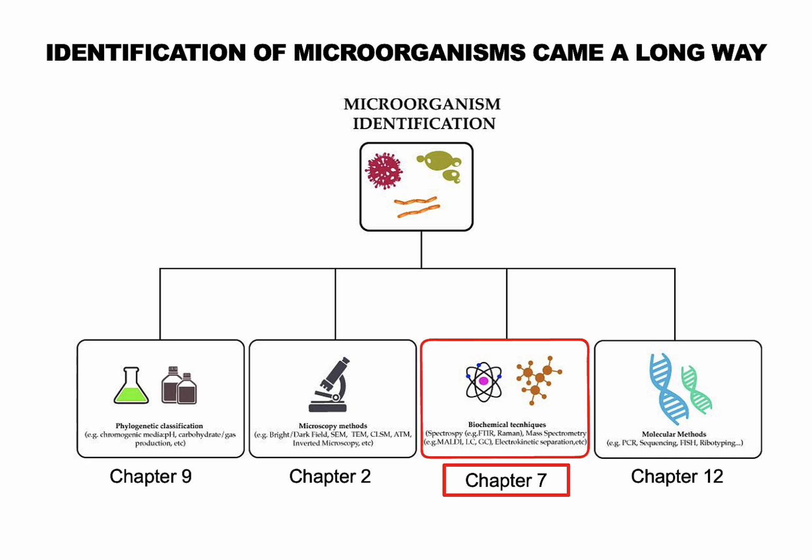The 1990s saw an emergence of automated identification methods that aimed to streamline and reduce the time required for analysis. Variations of the API system, such as BBL Crystal and the Vitek system, automate bacterial identification and antimicrobial susceptibility testing, AST, from patient samples. The Vitek system employs a broth microdilution technique monitored by an optical scanner to detect bacterial growth within 18 to 24 hours and yeast growth within 36 hours. While these systems offer versatility, some microorganisms may yield unreliable results.